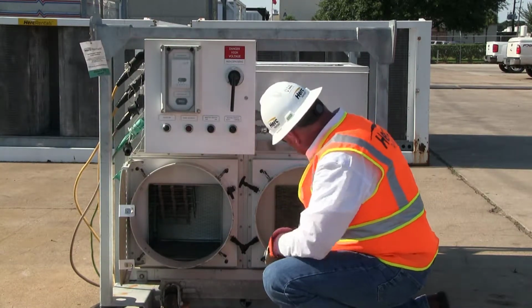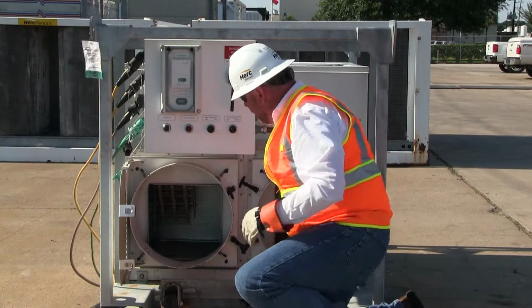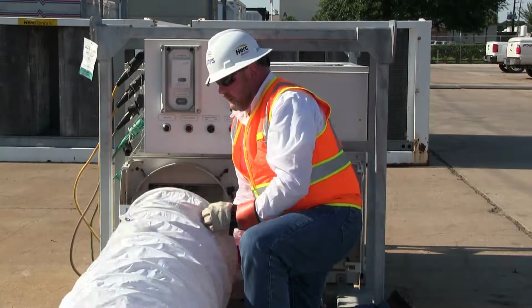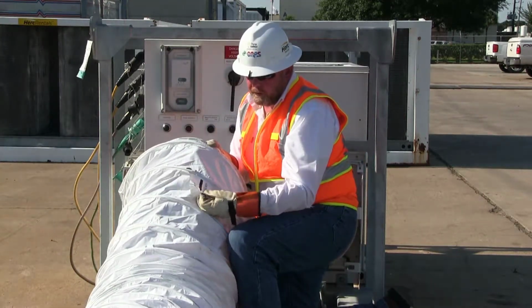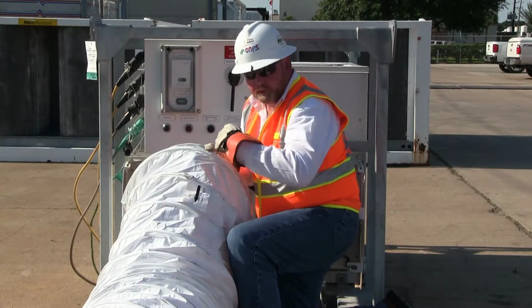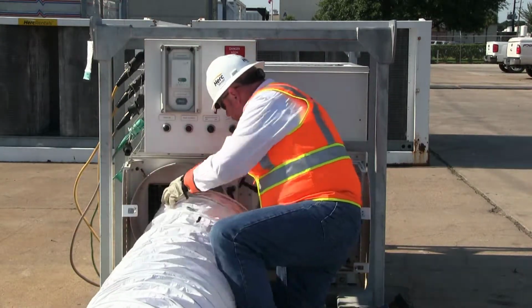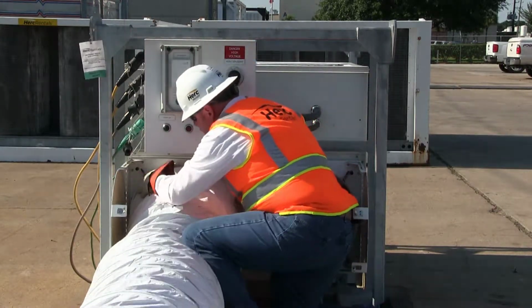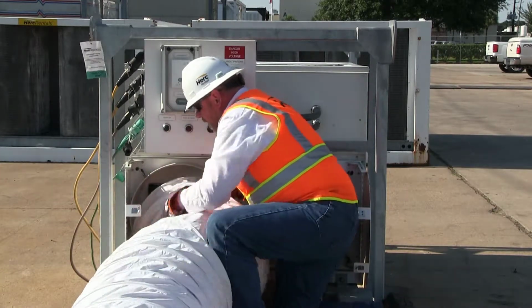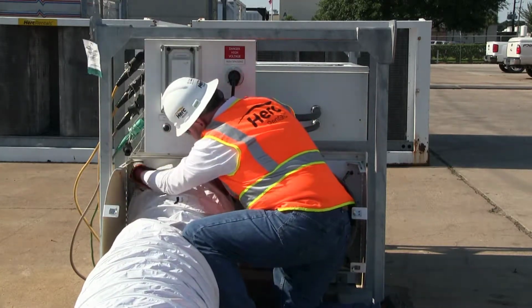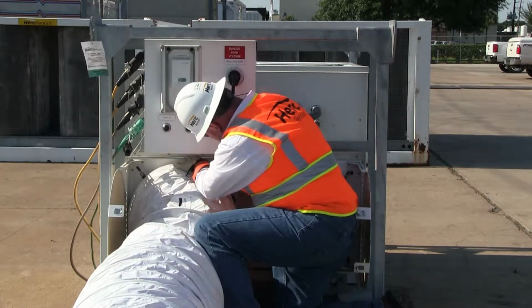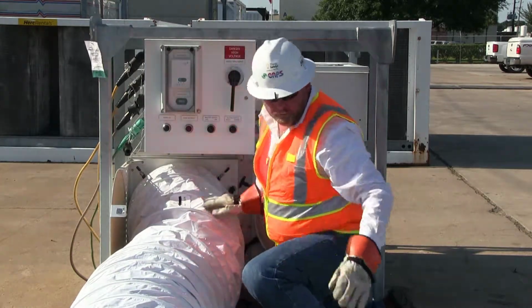Now you can see clearly we've got our intake and our supply. There's the heat strips there. You're going to want your ductwork to be going the correct direction. So this is our supply, it's going that way. We're just simply going to mount the duct up under the friction clamps, the friction rings that are in there on each of these, and lock these down in all four corners. We'll repeat that process on the return side.